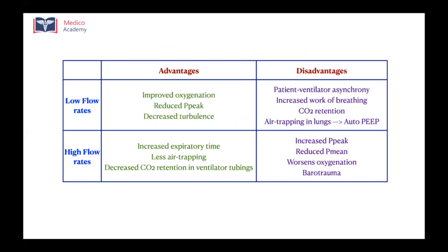If you keep a low flow rate, the gases will be uniformly distributed into the lungs, and that can result in improved oxygenation. The peak airway pressures will be reduced and there will be decreased turbulence. There will be less turbulent airflow. It will be a laminar flow of air into the lungs. So those are the advantages of low flow rates, where there is less turbulence, a reduction in the airway pressures, reduced chance of barotrauma and improved oxygenation.